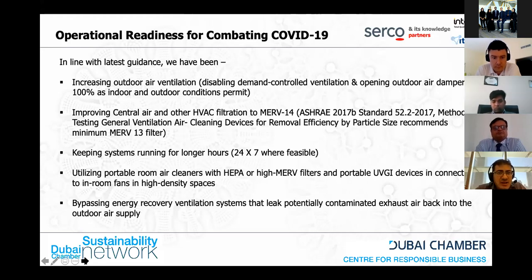In cases where 24/7 is not feasible, ASHRAE suggested that prior to the opening of the facility, 2 hours of 100% damper level should be used, and 2 hours after that, to basically flush out the stagnant air in the systems. Then using portable air cleaners with HEPA or high MERV filters, and portable ultraviolet germicidal disinfection devices. In connection to high density areas, bypassing energy recovery ventilation systems, which might potentially leak contaminated exhaust air back into the space. Next, please.